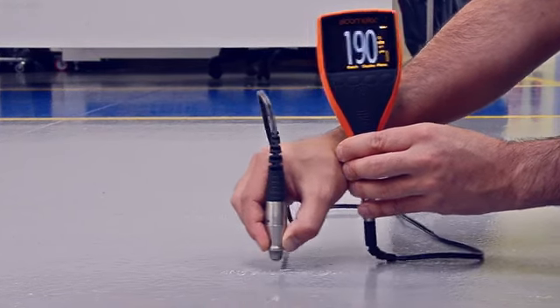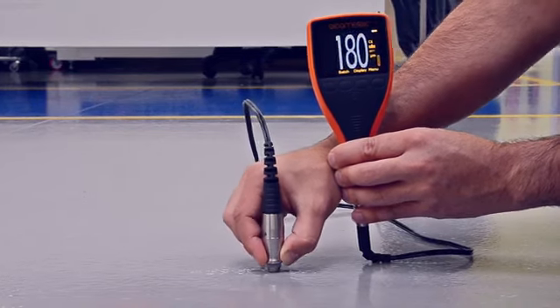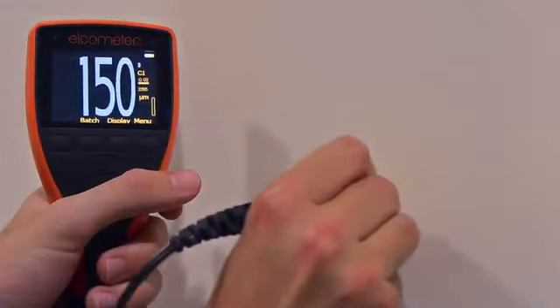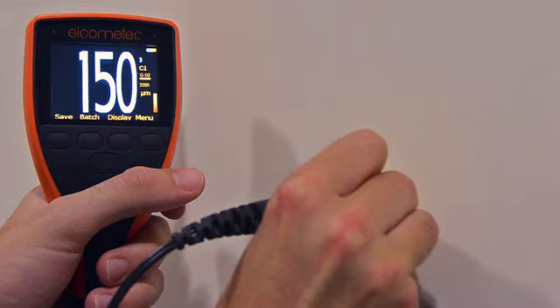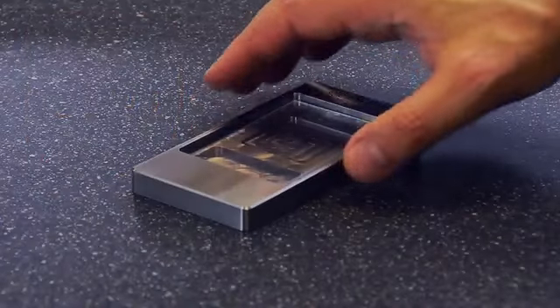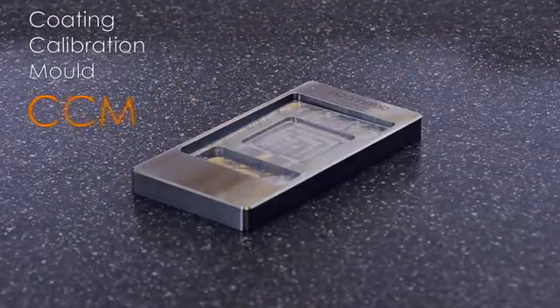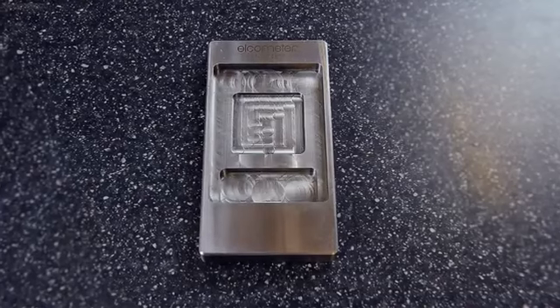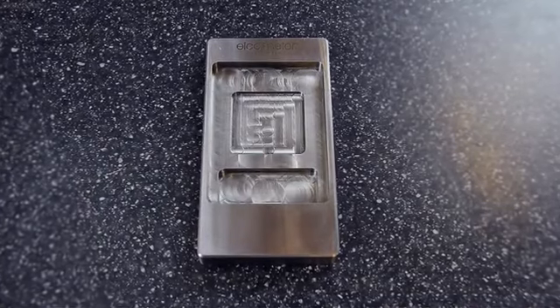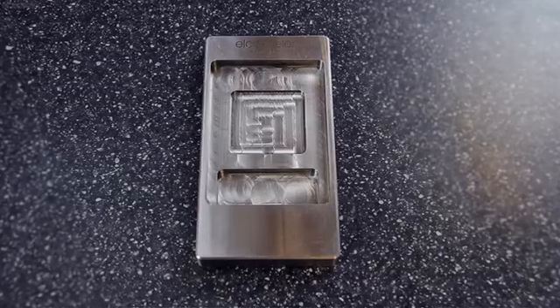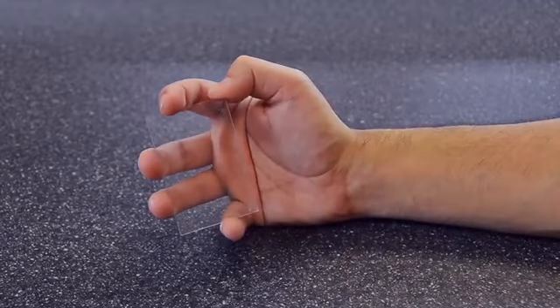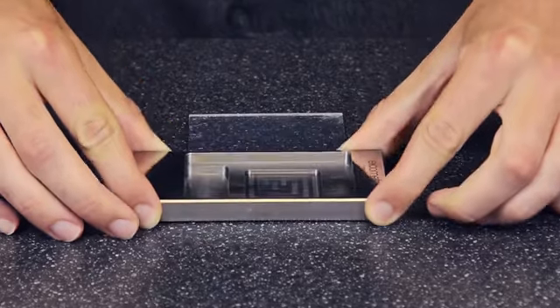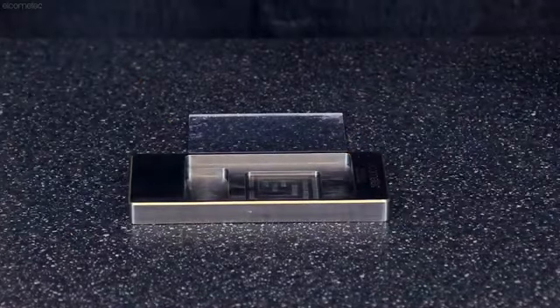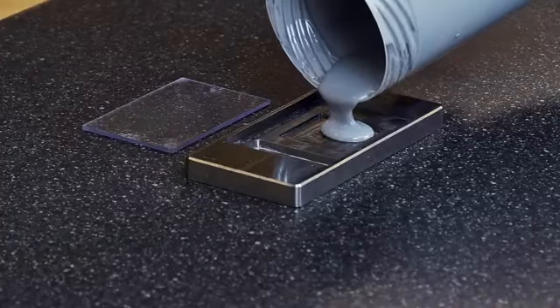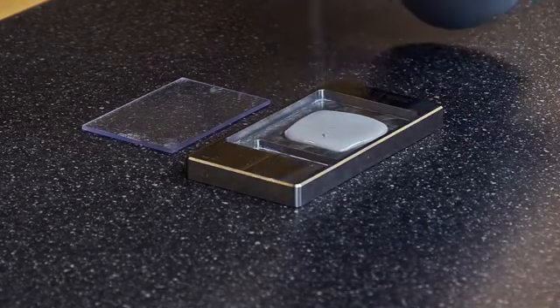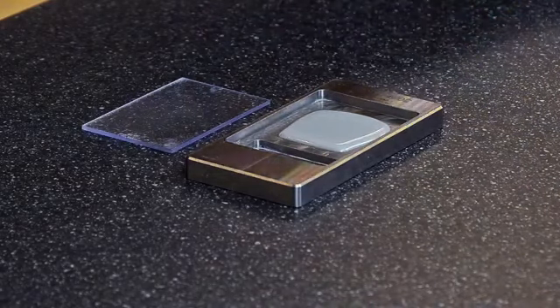If the speed of sound is not included on the coating manufacturer's datasheet, or is not already listed on your gauge's coating material list, then you can create your own calibration standard using the Elcometer Coating Calibration Mold, or CCM. The Elcometer CCM consists of a steel mold which has a sample and overflow chamber, together with a clear plastic scraper. Simply place the Elcometer CCM onto a flat horizontal surface and completely fill the sample chamber with the test coating, making sure that there is a slight dome or meniscus.